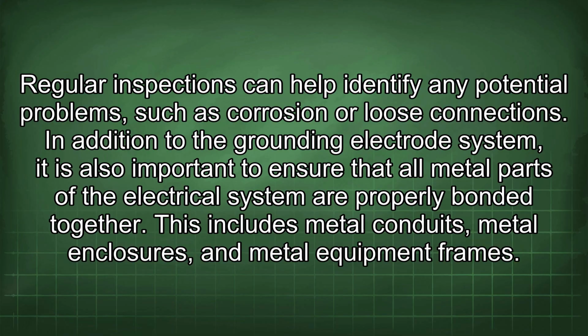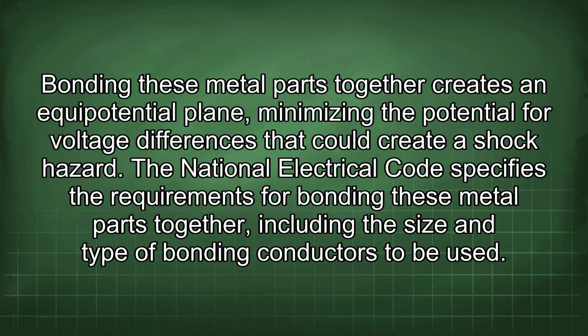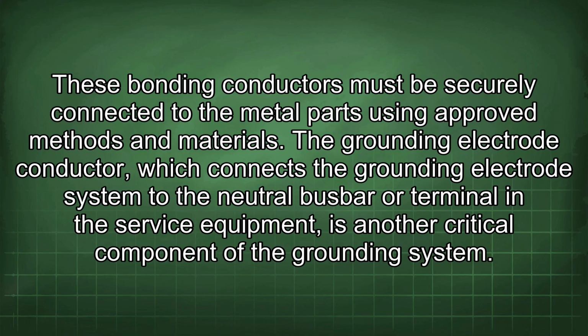In addition to the grounding electrode system, it is also important to ensure that all metal parts of the electrical system are properly bonded together. This includes metal conduits, metal enclosures, and metal equipment frames. Bonding these metal parts together creates an equipotential plane, minimizing the potential for voltage differences that could create a shock hazard. The National Electrical Code specifies the requirements for bonding these metal parts together, including the size and type of bonding conductors to be used. These bonding conductors must be securely connected to the metal parts using approved methods and materials.